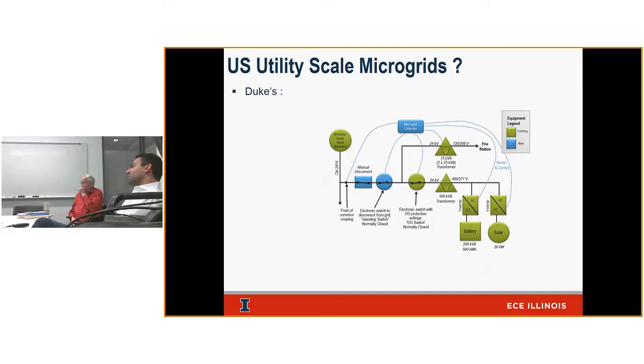Take note that this is centralized control, one controller controlling all these assets. If you lose that microgrid controller, the microgrid does not function properly. You won't be able to automate the operations of the devices. They'll depend on their own settings and protection schemes, but there's no coordination and control among all the assets.